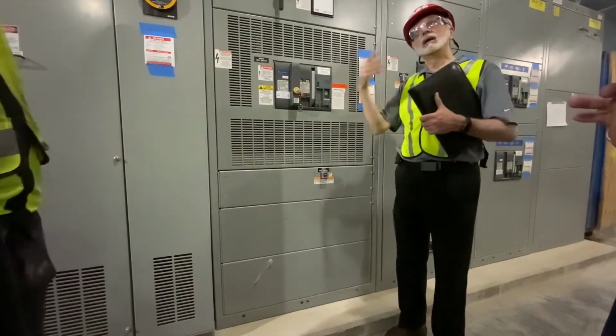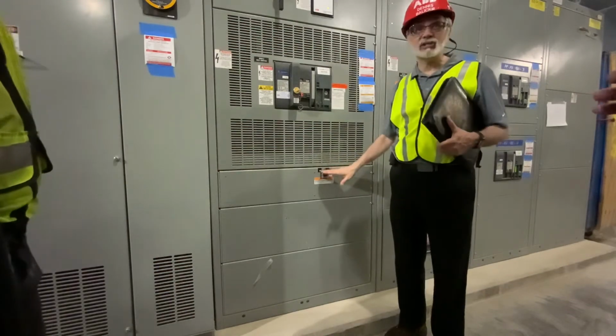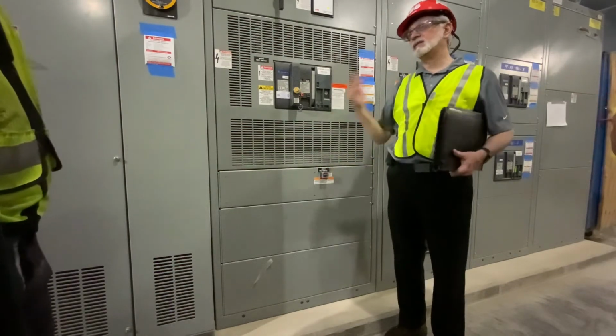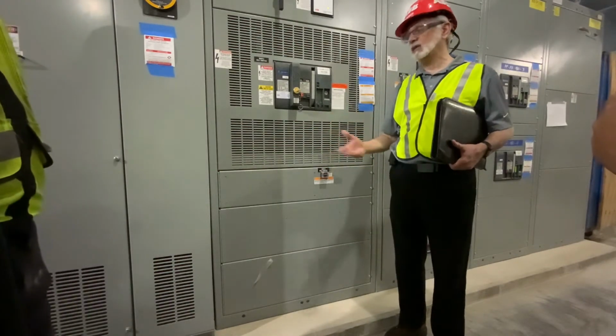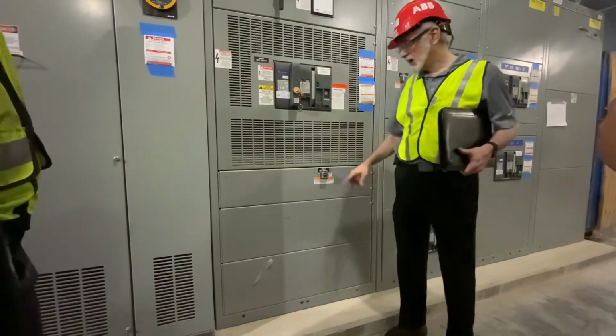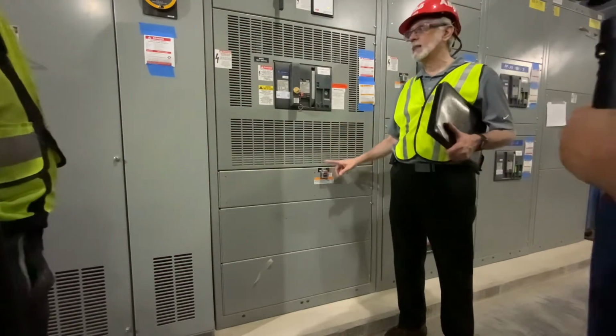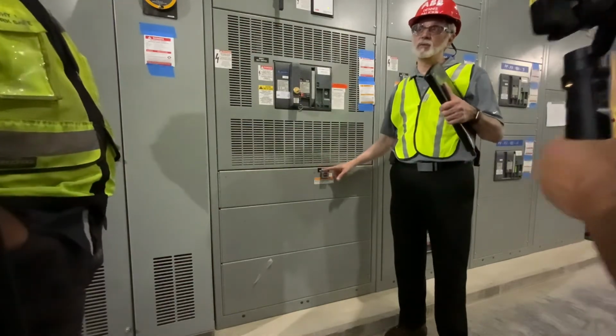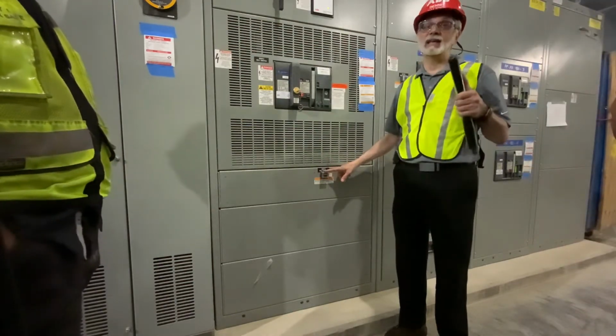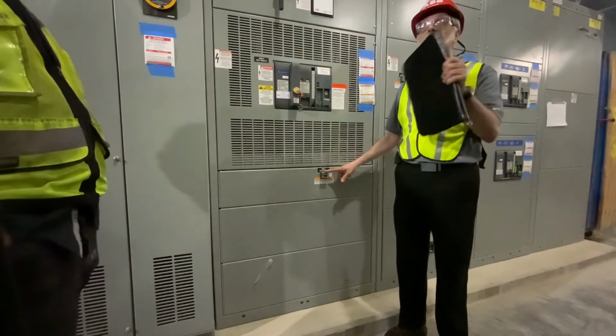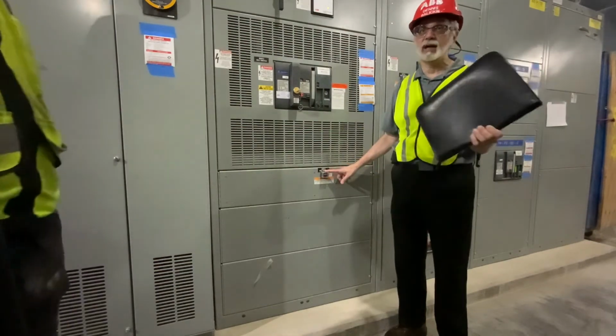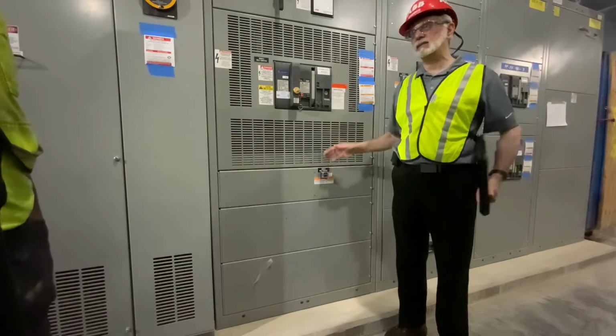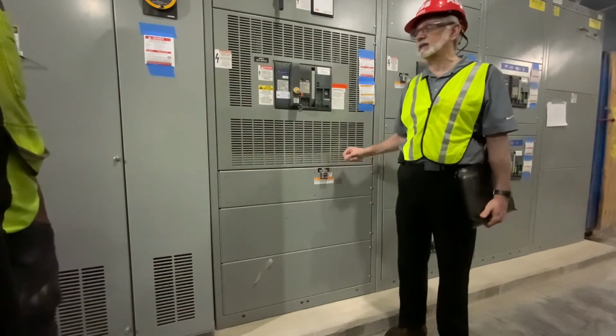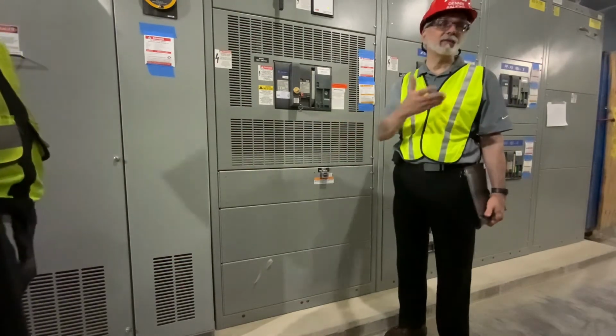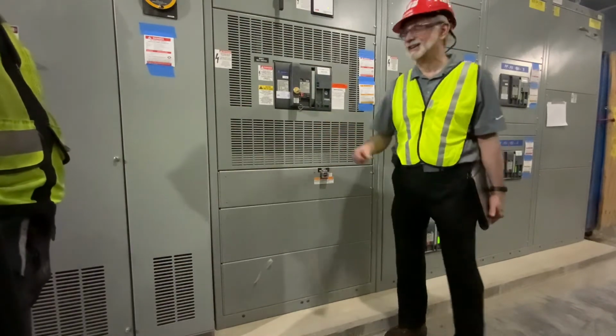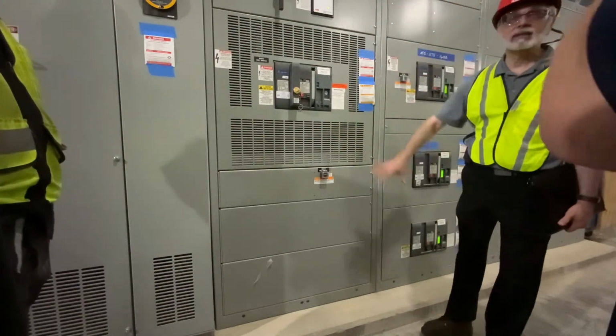Okay, so again, that's something that the National Electric Code requires. Pennsylvania and the city of Philadelphia is on that National Electric Code, so that's why you have this switch. It's there to minimize arc flash in energized situations. We still prefer you not to do energized work, okay? But this is the way that the National Electric Code mandates it, and this is better than having the breaker set at 10x, okay? So, any questions about the main incoming section?